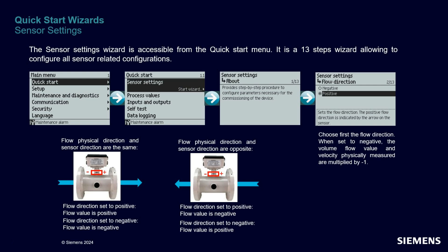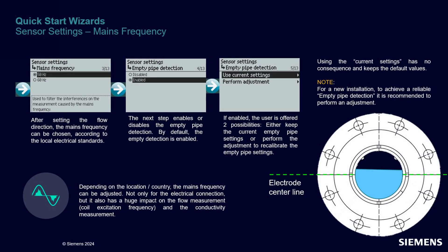Please note the sticker on the terminal box which indicates the normal positive flow. Next, you will set the frequency of the power source. You have the choice of 50 Hz or 60 Hz, and it is important for the performance of the magnetic circuit to pick the correct one.